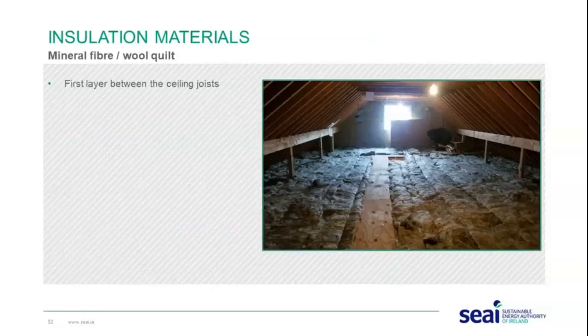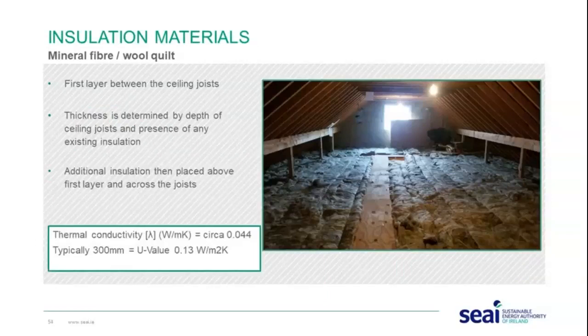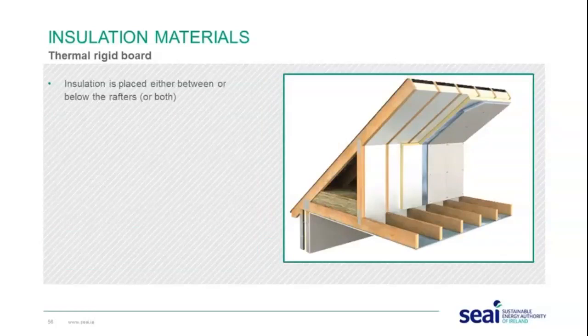For mineral fibre or wool quilt, you typically place the first layer between the joists — dependent on the thickness of the joists and any existing insulation — and then additional insulation is placed above the first layer and across the joists. The thermal conductivity for common mineral wool is 0.044, and you would need to install around 300 millimetres, which gives a U-value that exceeds the scheme requirement of 0.13.